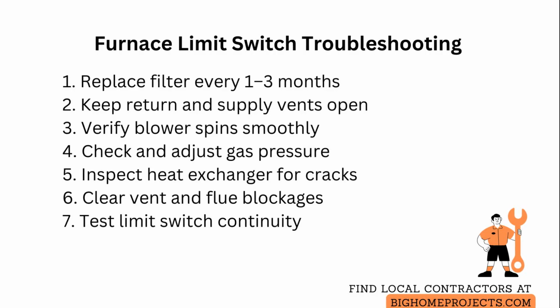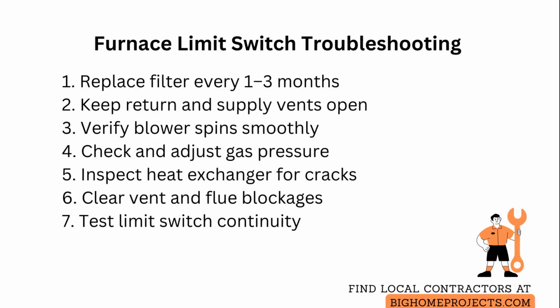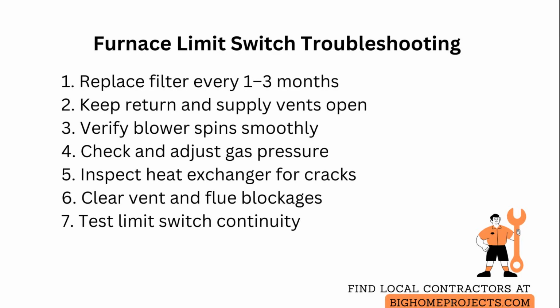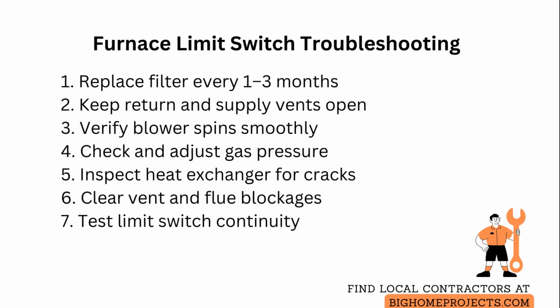Poor venting or blocked flue passages cause heat and combustion byproducts to remain in the heat exchanger area, so clear bird nests, debris, or secondary condensate blockages, and verify proper draft with a smoke pencil or draft gauge.